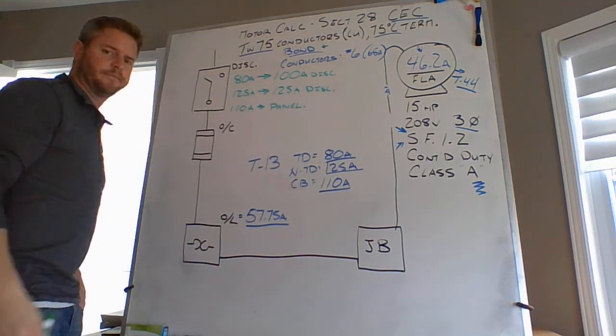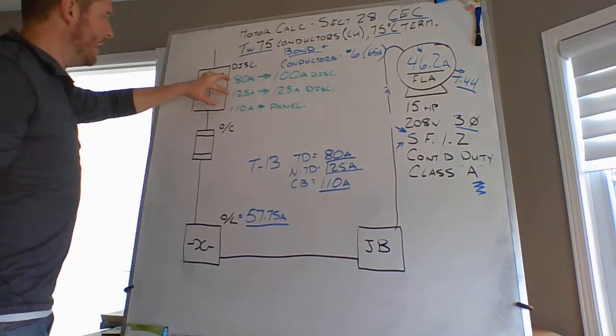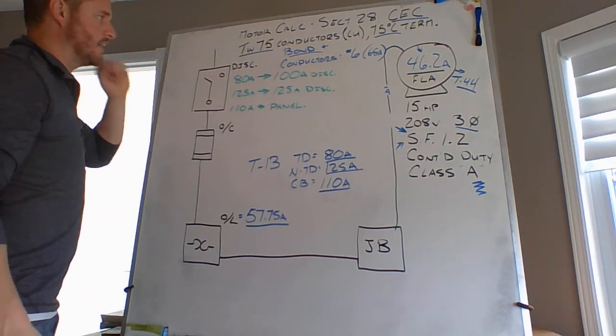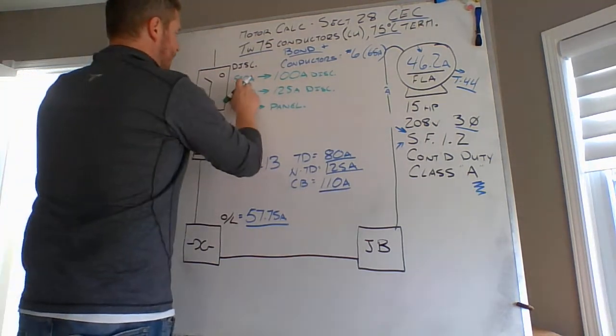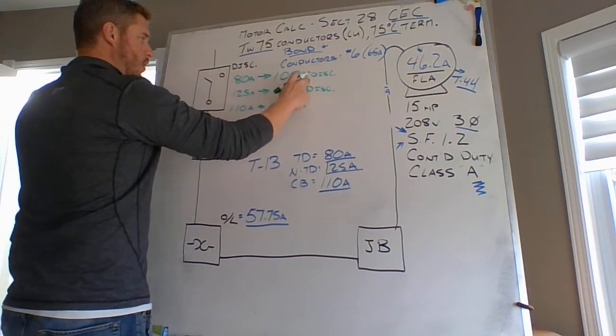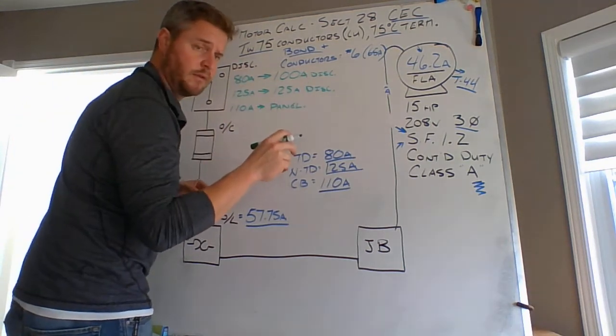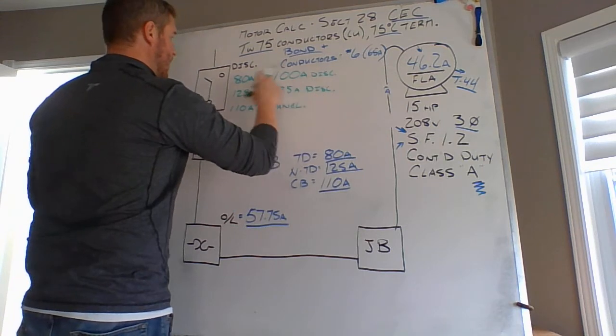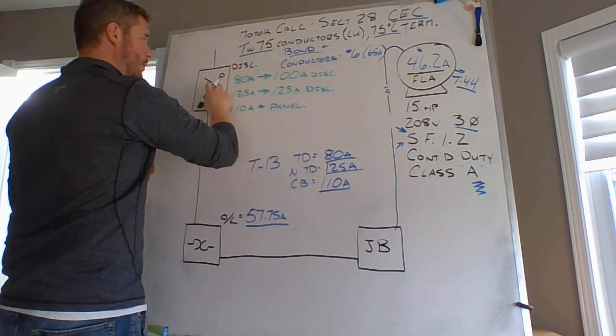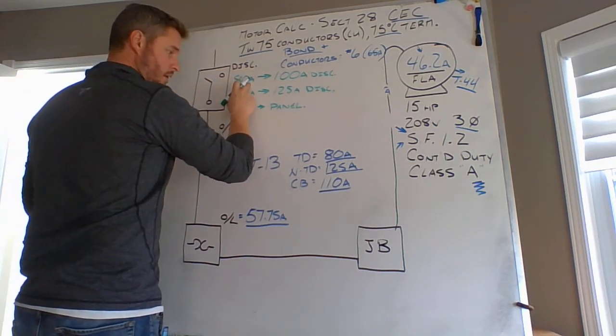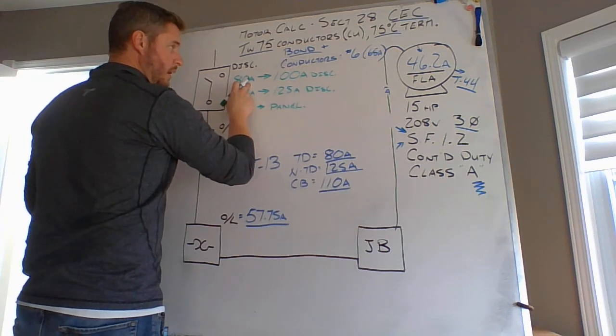That's no big deal. But these two values are interesting to us. Okay, 80 amp fuses going into a 100 amp disconnect. That's fine. I would size that disconnect to being 100 amps to accommodate an 80 amp fuse. That's no problem. We can get away with that.